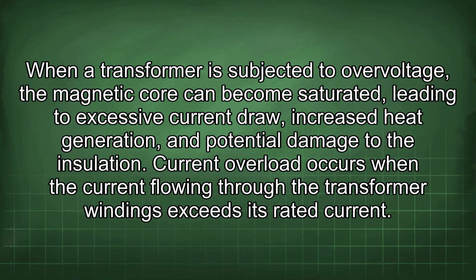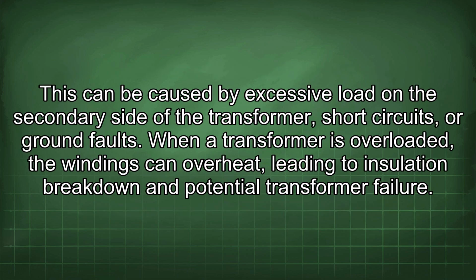Current overload occurs when the current flowing through the transformer windings exceeds its rated current. This can be caused by excessive load on the secondary side of the transformer, short circuits, or ground faults. When a transformer is overloaded, the windings can overheat, leading to insulation breakdown and potential transformer failure.